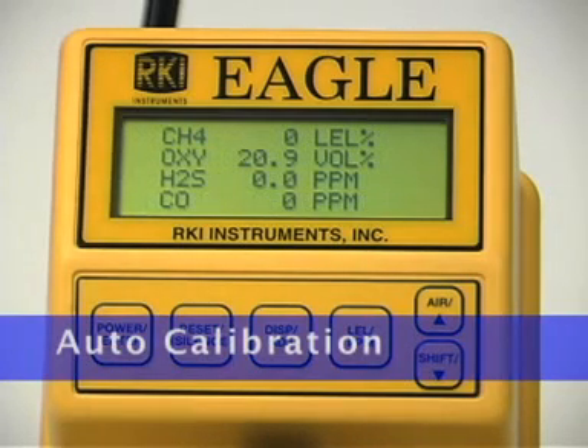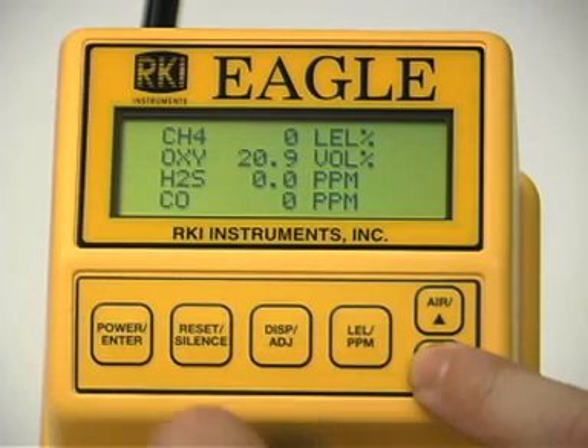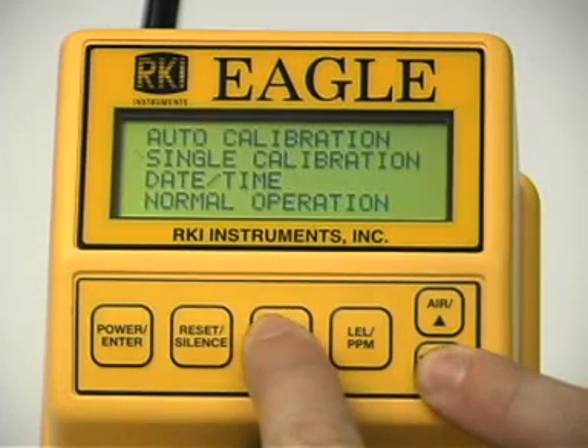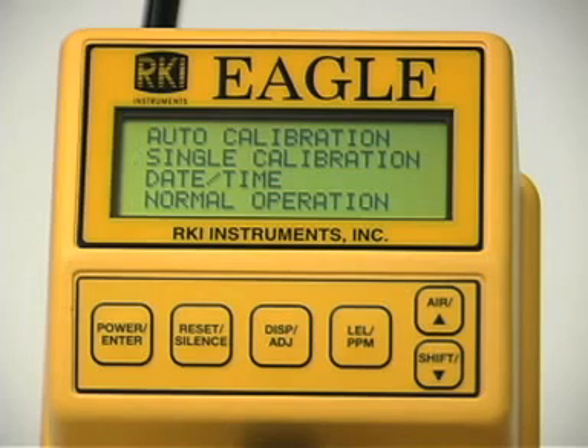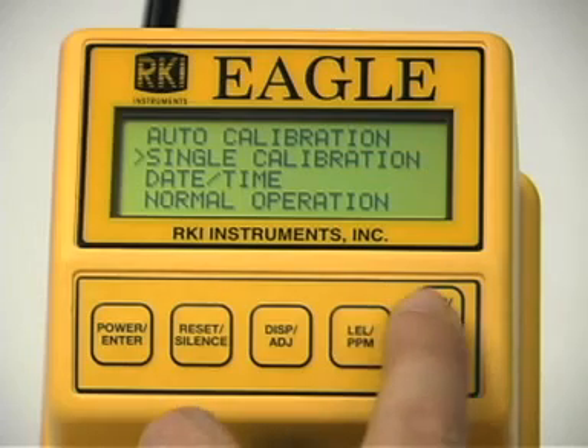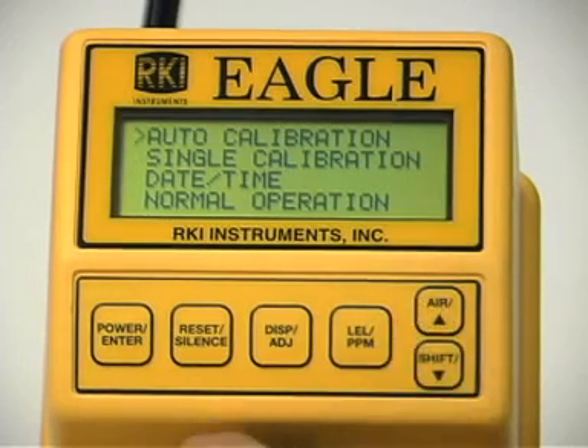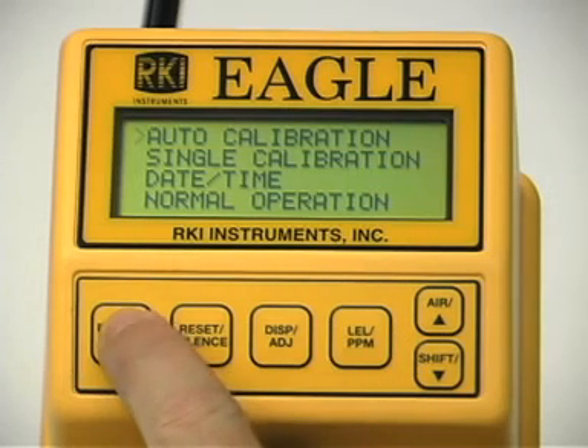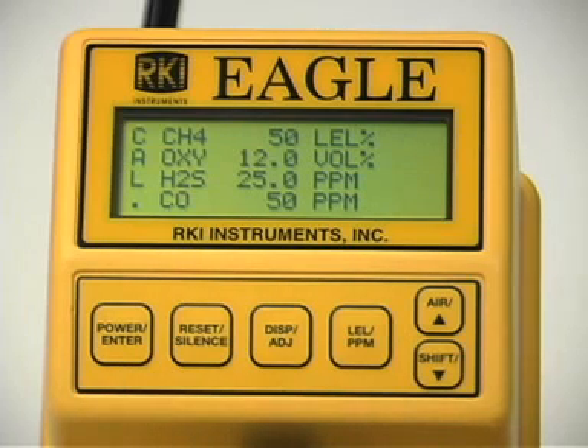To enter the calibration menu, press and hold the Shift Down button, then simultaneously press the Display Adjust button. Your Eagle may display slightly different gases depending upon your Eagle's configuration. To calibrate using the auto calibration method, use the up or down button to place the prompt next to the auto calibration menu option. Press the enter button to display the calibration values screen. The gas concentrations displayed in the calibration values screen must match the gas concentrations listed on the calibration cylinder. If all concentrations match, press the enter button. The gas readings will begin flashing.